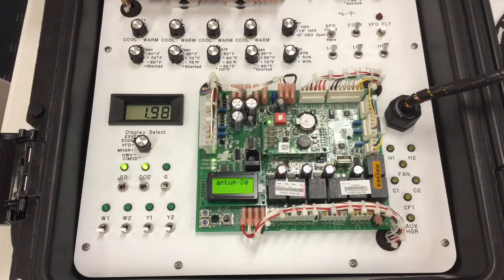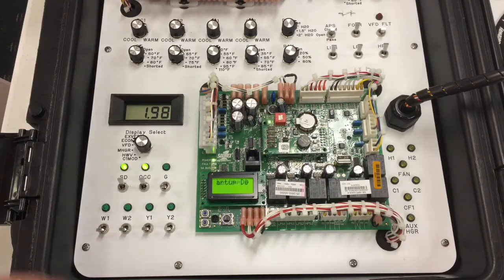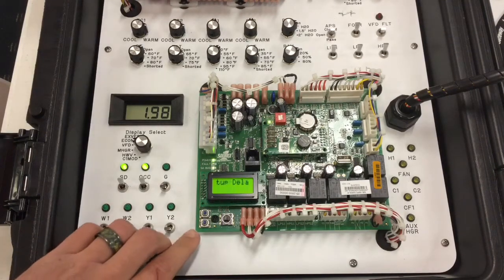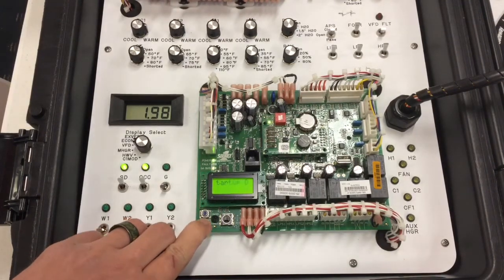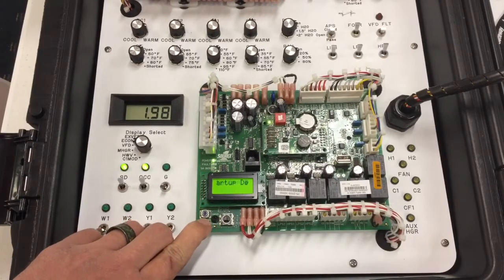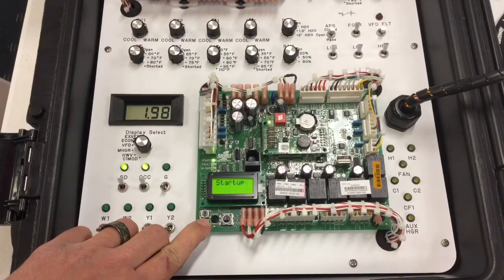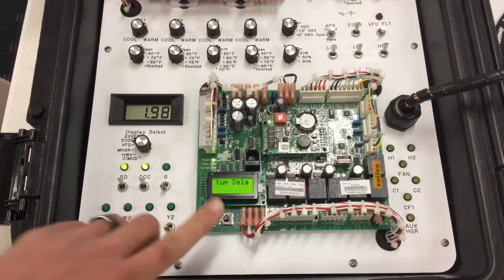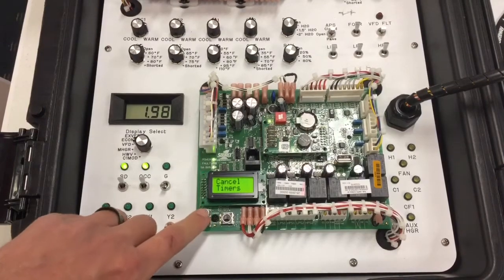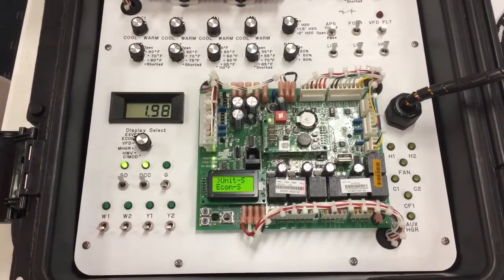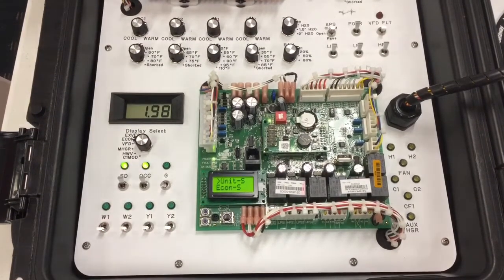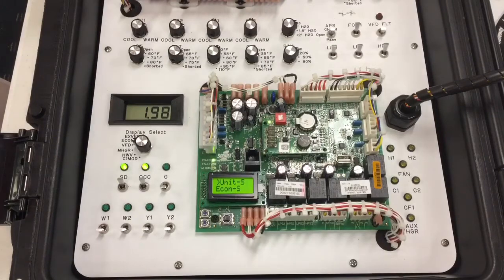In order to bypass the startup delay, you simply press and hold the cancel button for about five seconds. Once you release the cancel button, it will ask you if you want to cancel timers. Release and press the enter button one time. Now my compressor anti-short cycle time delay has been bypassed.